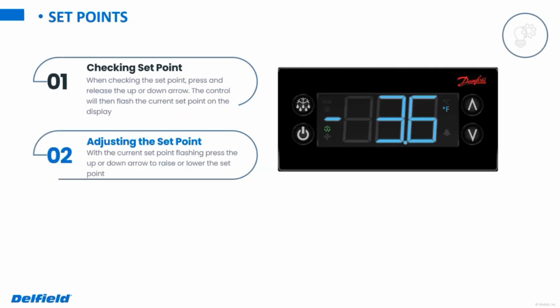As far as adjusting the set point on these, this one's pretty easy. You just press the up or down arrow one time. The unit should flash the current set point. So if it's a freezer set at 0 degrees, it'll flash and show 0. Maybe you want to bump it up a couple degrees. While it's flashing, you can press the arrow on the top. You can press and hold it if you're making a big adjustment, and then you can stop at whatever set point you'd like. It'll flash for a few seconds and then automatically save it. So that's a pretty easy way to adjust the set point on those.